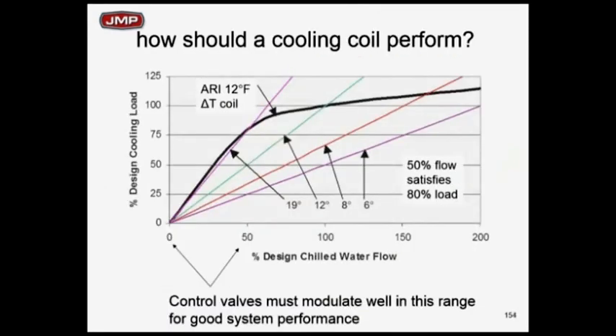So let's get away from the product a little bit and get over to what we're trying to do. Here's a typical ARI certified cooling coil. Real quick, this coil was picked for 12-degree delta T at 100% load, which is the vertical axis on the left, at 100% flow, which is the horizontal axis on the bottom. If I go to 100% chill water flow, go straight up to the solid black line, you'll see to the left 100% load, and the solid black line is 12-degree delta T. Great. That's what you expect.